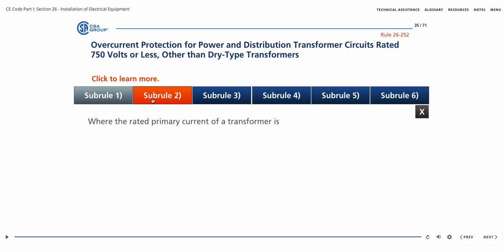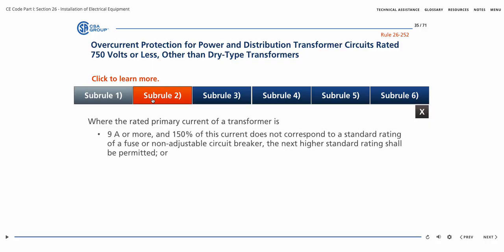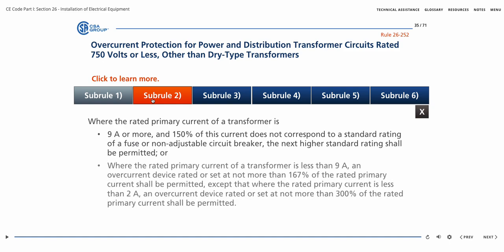In Subrule 2, where the rated primary current of a transformer is 9 amps or more, and 150% of this current does not correspond to a standard rating of a fuse or non-adjustable circuit breaker, the next higher standard rating shall be permitted. Or, where the rated primary current of a transformer is less than 9 amps, an overcurrent device rated or set at not more than 167% of the rated primary current shall be permitted, except that where the rated primary current is less than 2 amps, an overcurrent device rated or set at not more than 300% of the rated primary current shall be permitted.